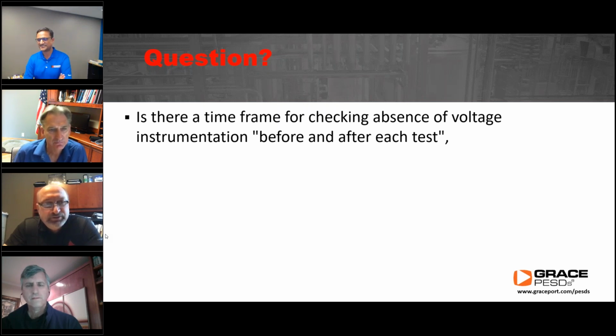If you're going to test a conductor and circuit part for absence of voltage, you do it right before you make bare hand contact. You test your test instrument, test before touch, at that point in time - then you've truly established an electrically safe work condition. You maintain that condition when you're not wearing PPE and doing de-energized repair or alteration work. So you test your instrument on a known source, test it on the target conductors and circuit parts to confirm zero voltage, then retest your instrument to make sure it was functioning. At that point, as long as you follow the other requirements for establishing an electrically safe work condition, you should be able to remove your PPE and do the de-energized repair and alteration of the components you found failed.